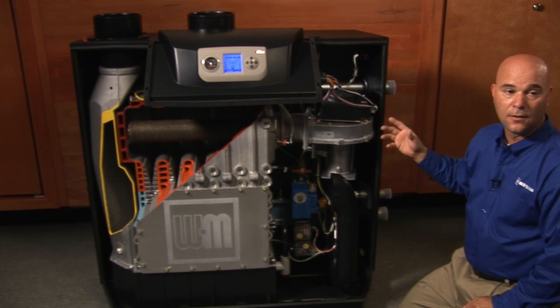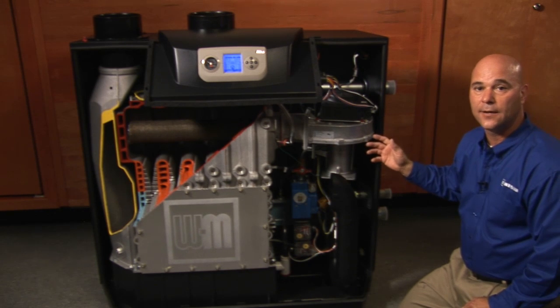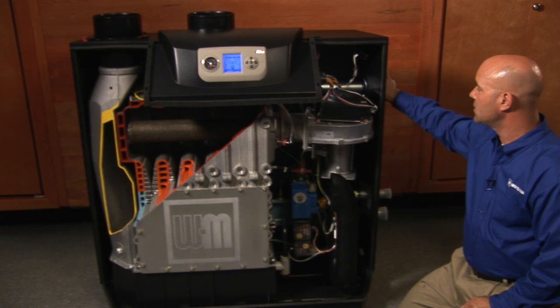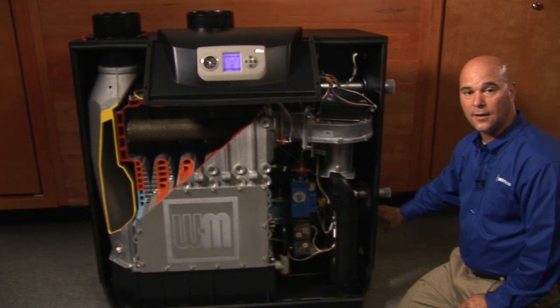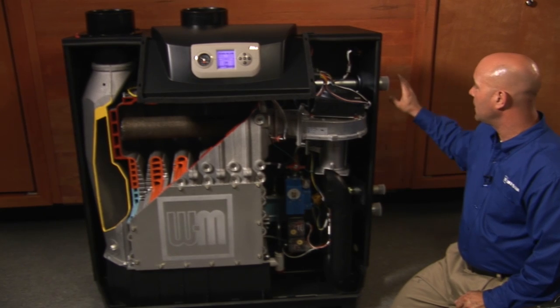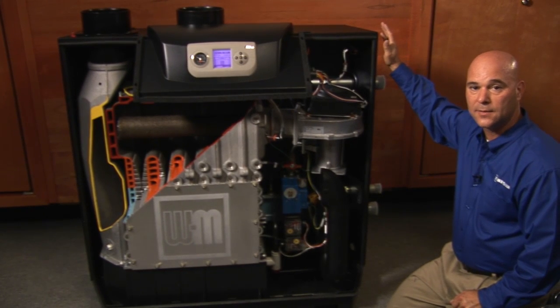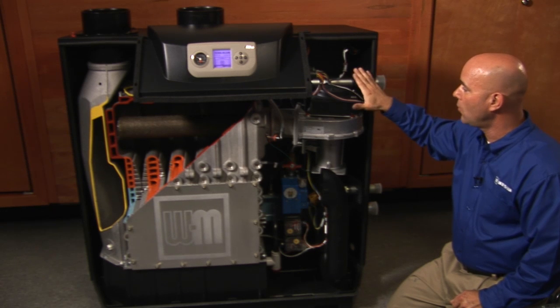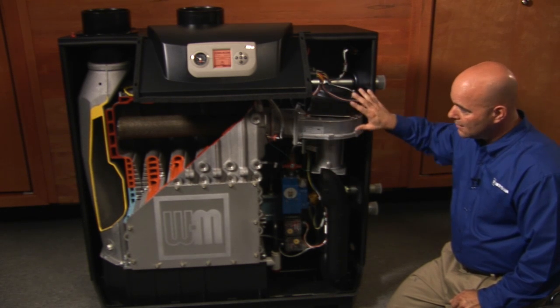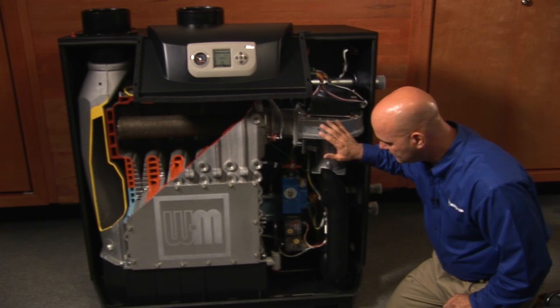The boiler still needs to be piped primary, secondary. So you got a 2-inch supply, you have a 2-inch return. We're going to take them out, we're going to do primary, secondary piping. That's a tour of the heat exchanger compartment.